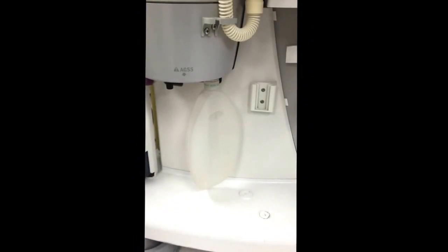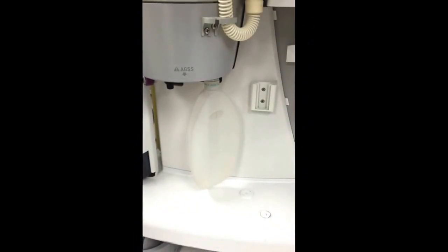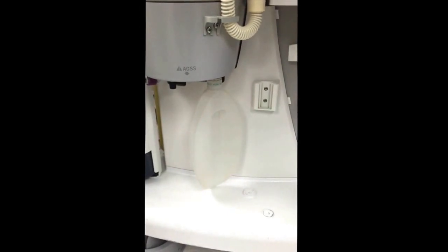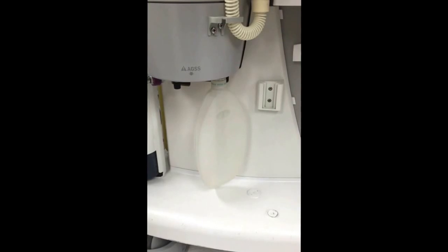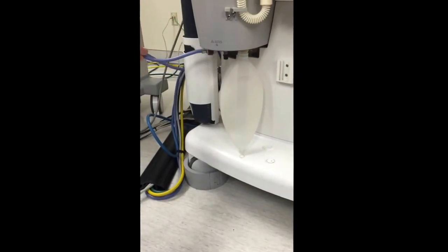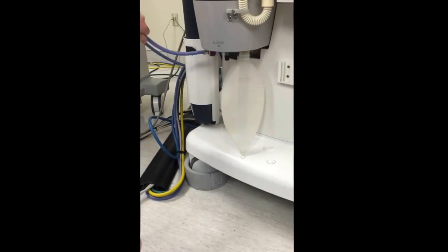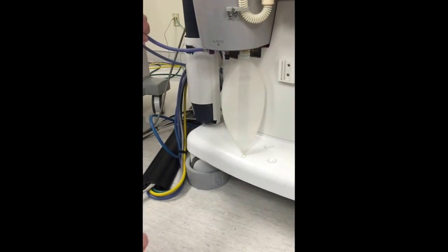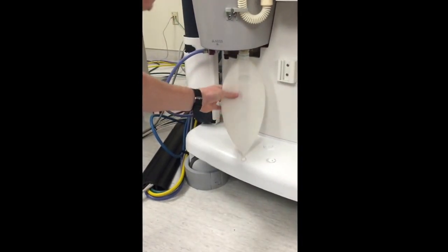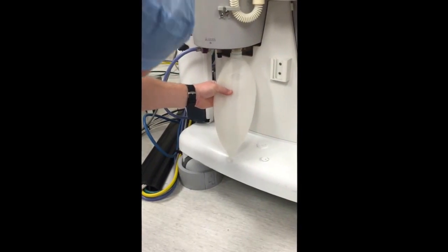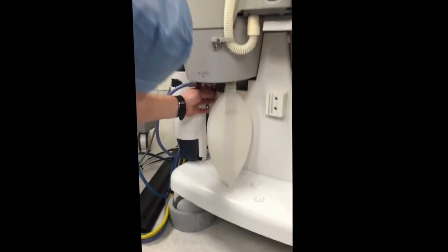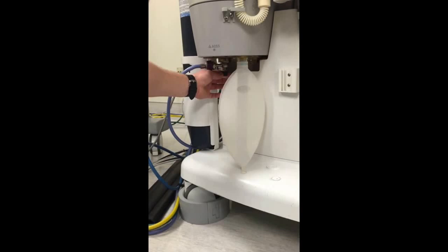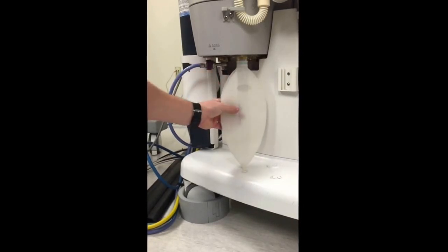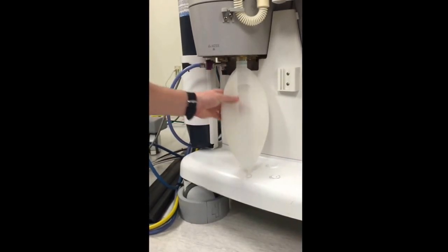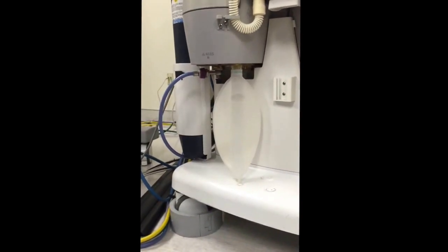Check your scavenging system by turning the APL valve completely off, and the scavenging system is functioning correctly. This is your active system, which takes your inhalation agents and waste gas out of the OR. This is your bag that always has somewhat of a negative pressure, and this knob right here is where you would adjust that pressure. So it should always be deflated to know that the gases are being correctly scavenged.